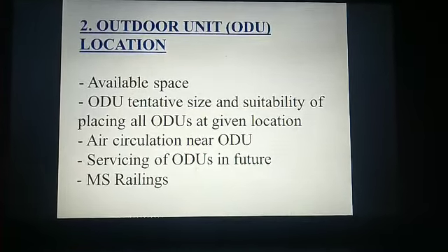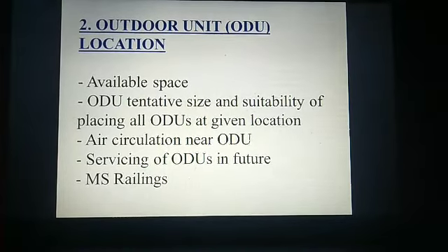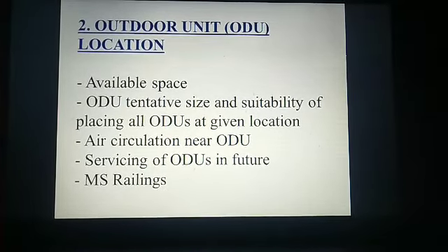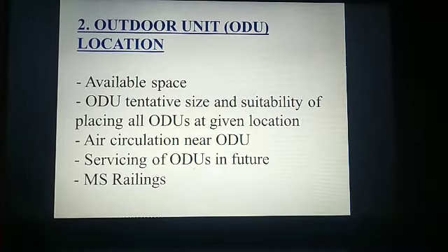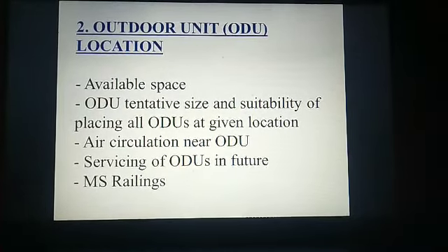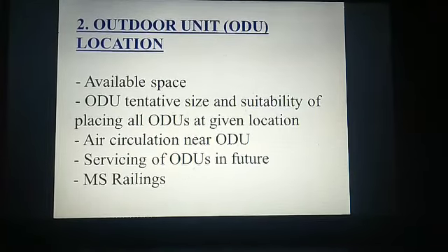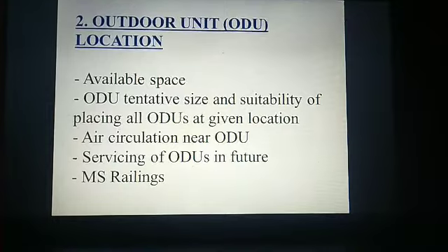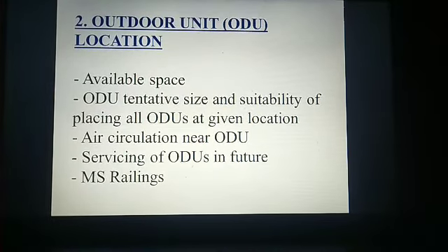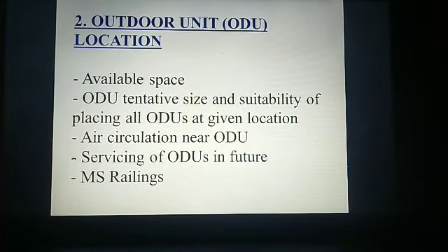Second point is outdoor unit location. Once system is finalized, now check for outdoor unit location. Check whether all outdoor units can be properly placed or not. Check whether there is sufficient space available around outdoor units for air circulation. If proper air circulation is not there, cooling issues may arise in future.